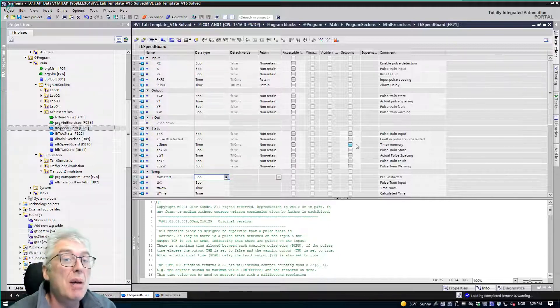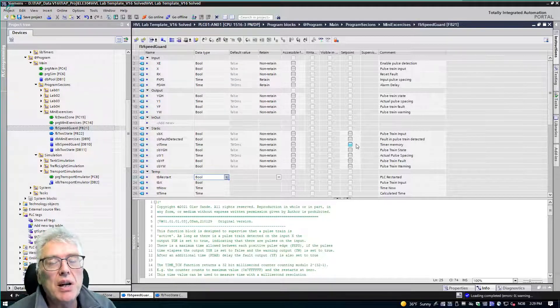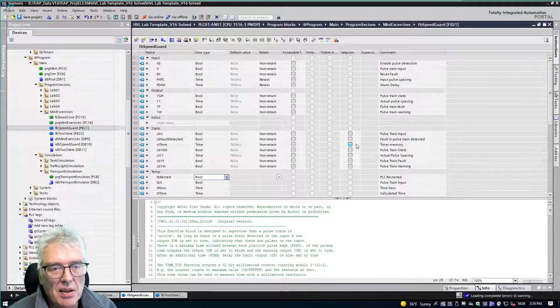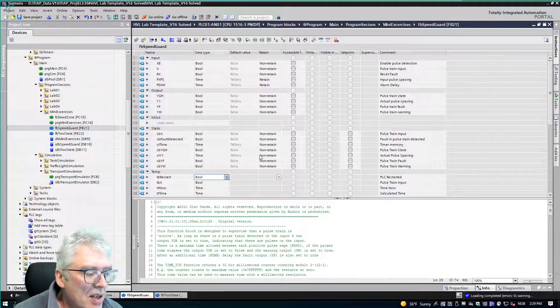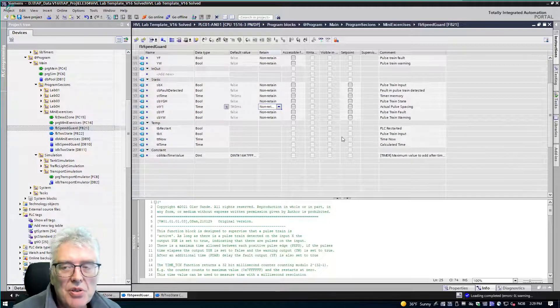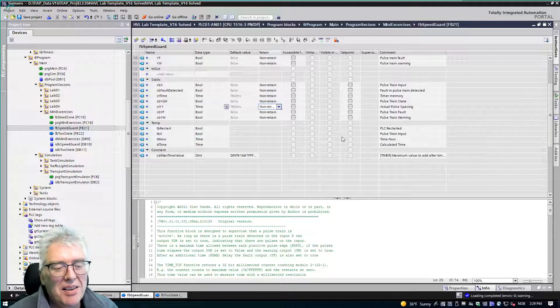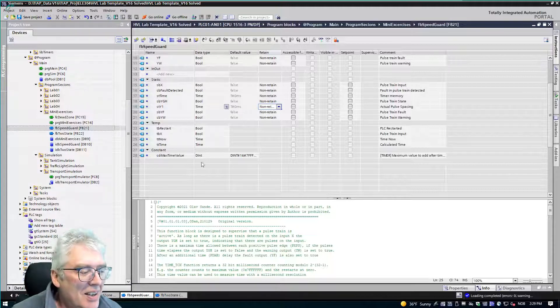Here are the internal static variables. Static variables always retain their value — whatever I write to them stays as long as the PLC has power. Temporary variables do not have that property; they are forgotten each scan cycle. And there is a constant defined down here as well.